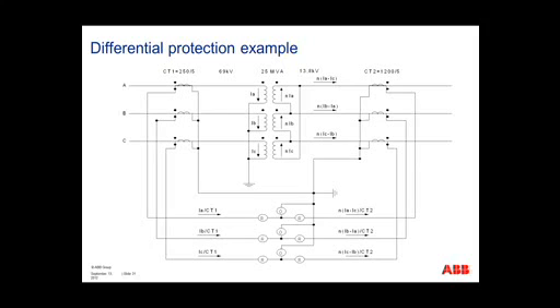So let's look at a differential protection example. Here we're showing a 69 to 13.8 kV transformer, 25 MVA. We notice by the connections that we have a Wye-Delta connected transformer. On the high side is Wye, on the low side is Delta. If we look at our CT ratios, we have a 250 to 5 CT ratio on the high side and a 1200 to 5 CT ratio on the low side. This is because, of course, we have lower current on the high side and higher current on the low side. So we have accounted for the current difference on both sides of the transformer by our CT ratios.